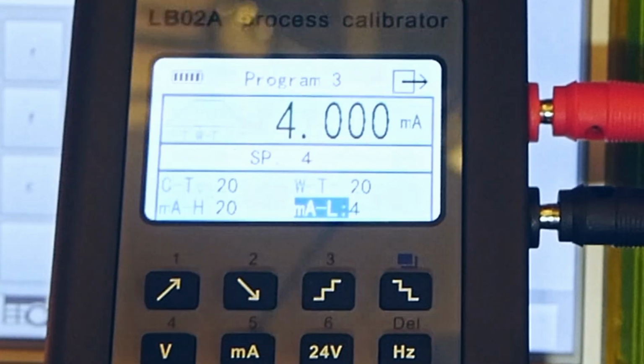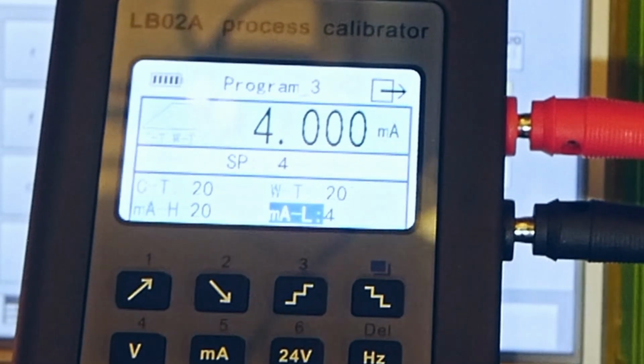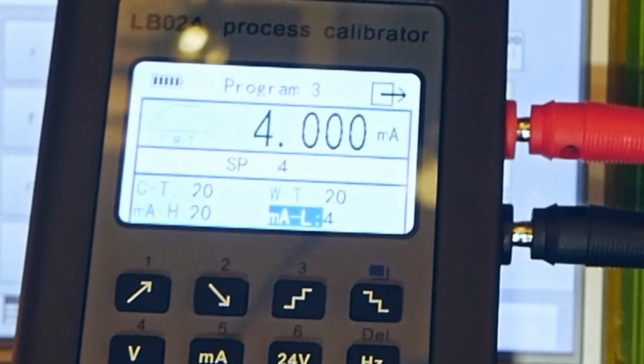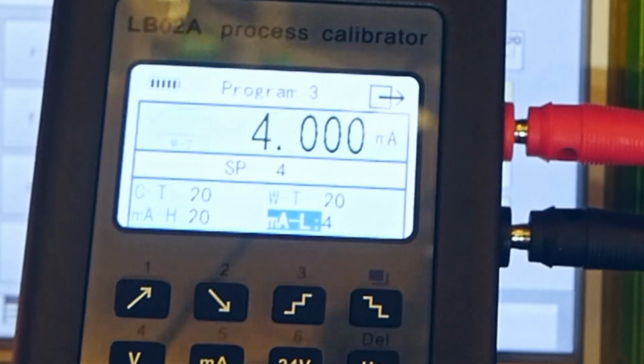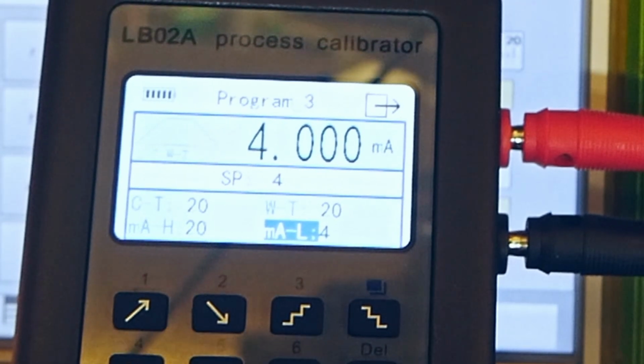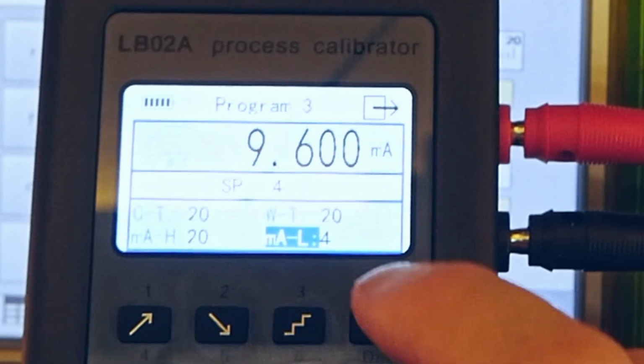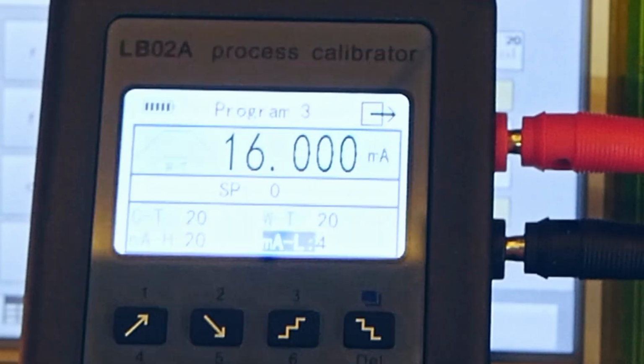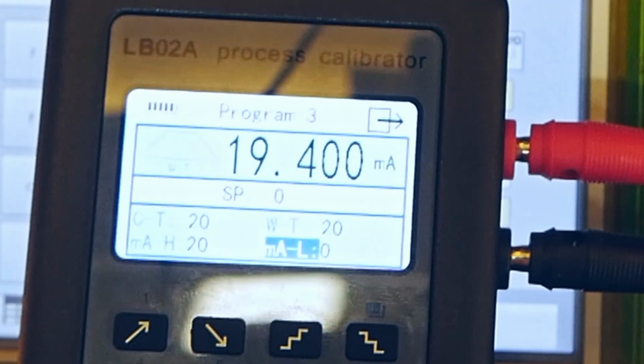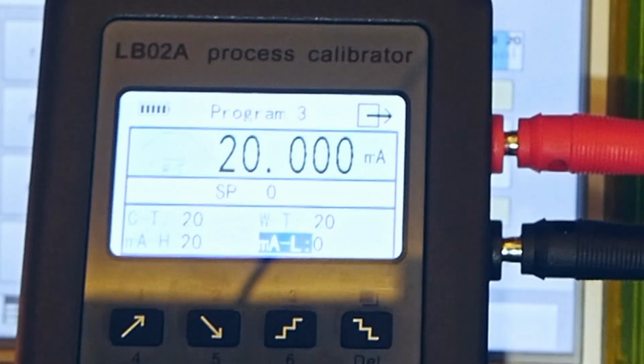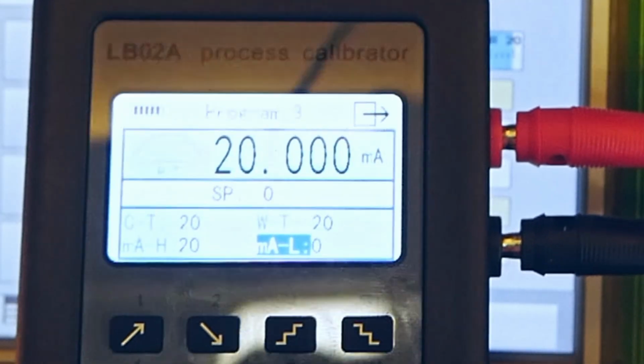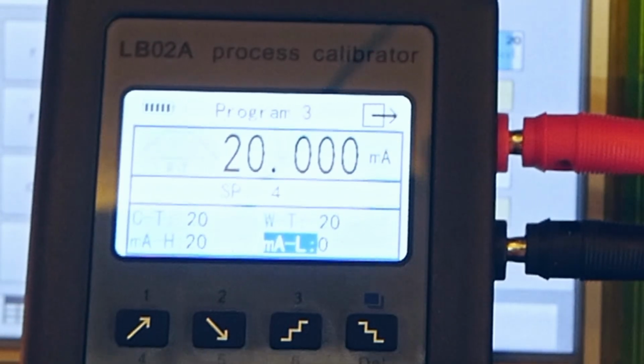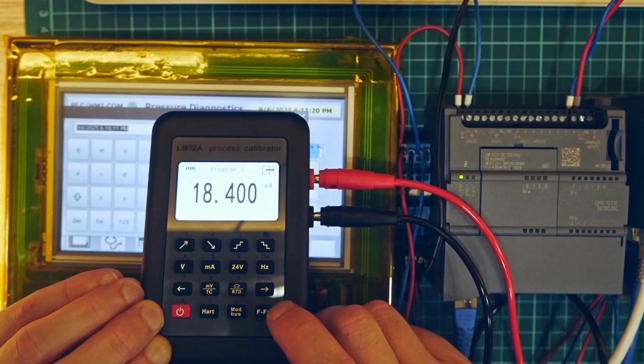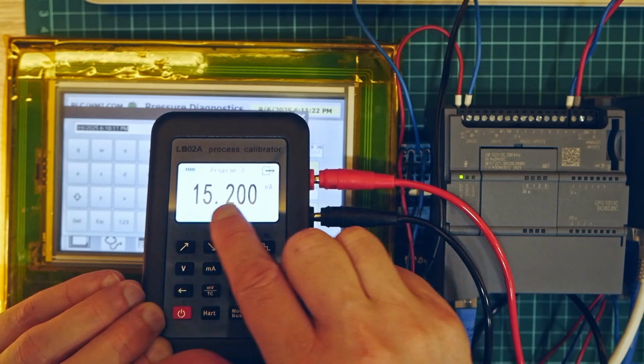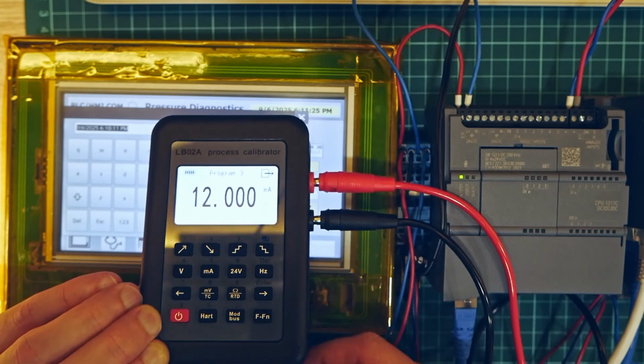So we are simulating system, okay, from 4 to 20 milliamperes. Your sensor could be from 0 to 20 milliamperes, so there is no issue. You can delete it and put here 0. But my system from 4 to 20, so I will enter set point 4. So if we go back from function, as you can see, it goes ramp up and ramp down.